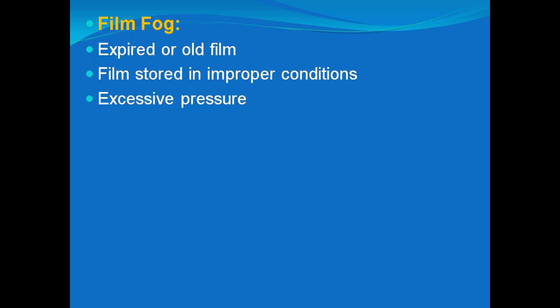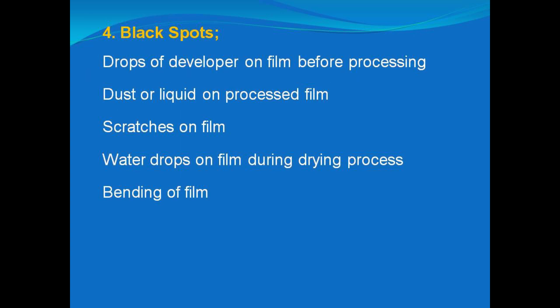Film fog can also result from film stored in improper conditions, film kept under excessive pressure, or due to stacking of the boxes of film.